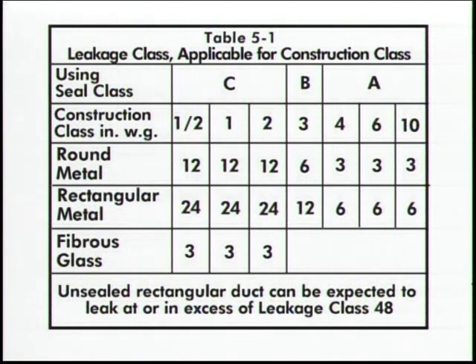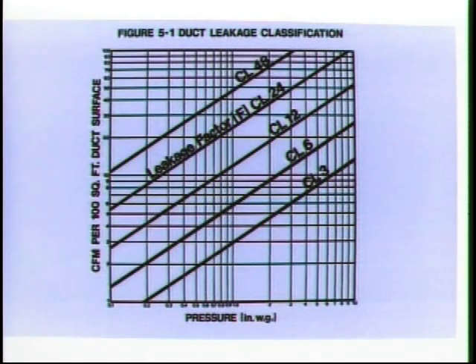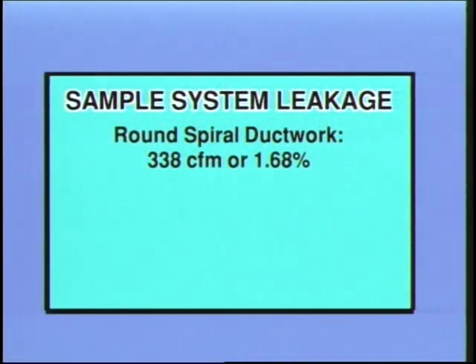Duct air leakage calculations for the 3 duct construction methods used for the sample VAV system require the use of square feet of duct surface. Note that the smaller perimeter of the round spiral duct discussed earlier now greatly affects duct leakage, because the perimeter multiplied by the duct length equals the duct surface. The ASHRAE duct air leakage table is based on 100 square feet of duct surface and the average internal duct static pressure. Duct air leakage calculations for the round spiral ductwork in the sample system total 338 CFM, or 1.68% of 20,100 CFM.